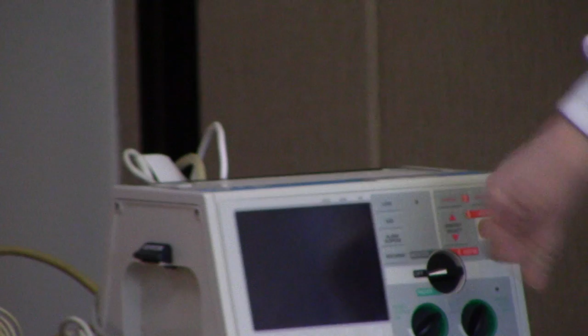The first step is to push the power button on the front of the monitor. The green light above the power button will blink, and then it remains lit. Hold the reader, which looks like a computer mouse, directly over the patient's implanted device to begin the interrogation. Please note, you can only retrieve information from the patient's device. You cannot change the programming in the device or turn off the device. While the reader is over the device, the following takes place.